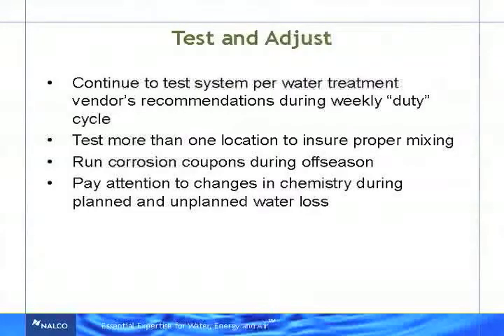Test more than one location during this period. Typically what you're going to see for water treatment testing is you've got your rack on the wall. It's got a little spigot there. You take the sample from there. During normal operation, that's fine. Water mixes enough. Your towers are mixing.